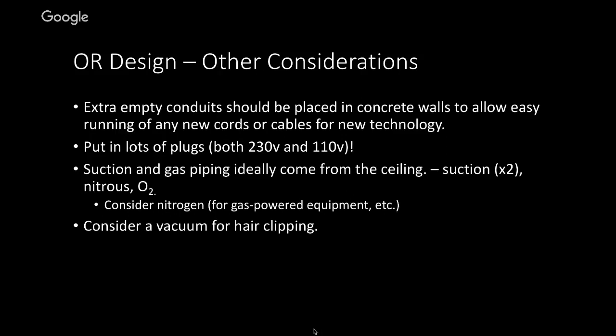That makes more sense. Ideally we run suction and gas piping for oxygen, nitrous, etc. from the ceiling. If you have the luxury and can get compressed nitrogen for gas-powered instruments, that's fantastic. If you're doing hair clipping in the operating room, have a vacuum.